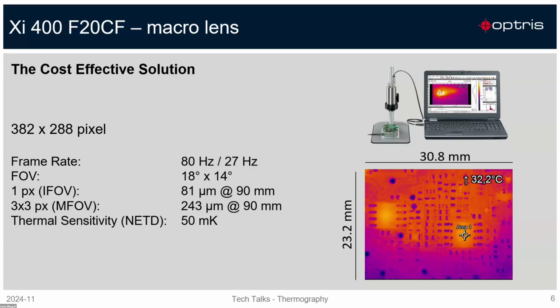And at a distance of 90 millimeter, you can have with this camera a horizontal field of view of 30 millimeters and a vertical field of view of 23 millimeters. Yeah. So we are talking here about 1 pixel. And if we have the MFOV, that means a matrix of 3 × 3 pixels, we have 243 micron at a distance of 90 millimeter. The thermal sensitivity of this camera is 50 millikelvin.